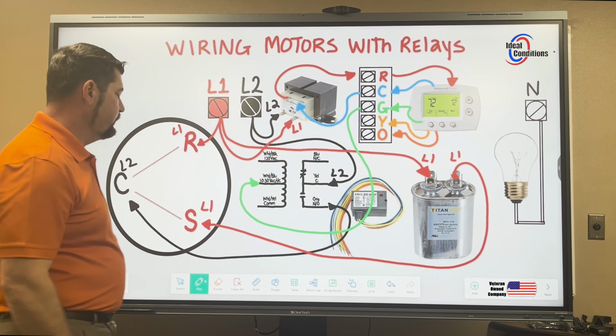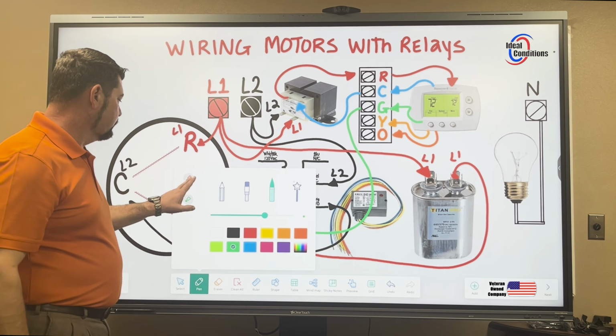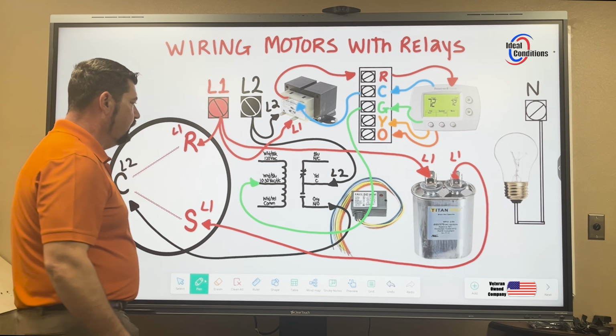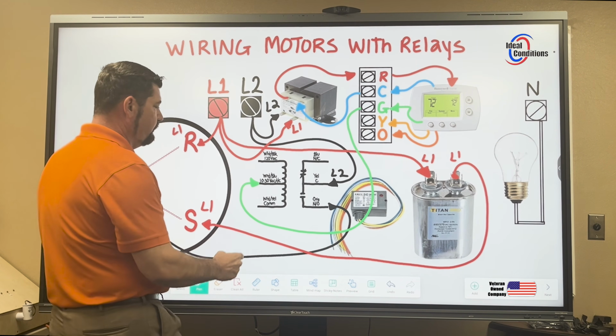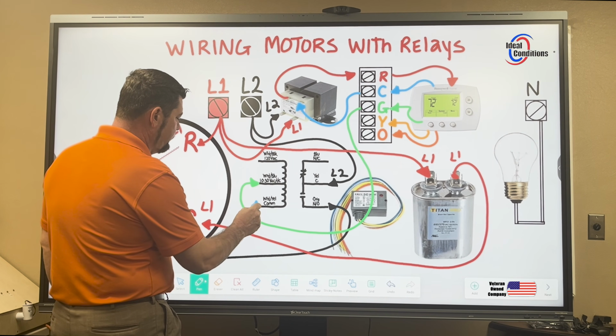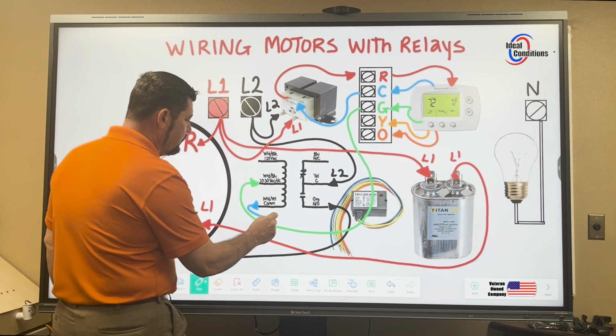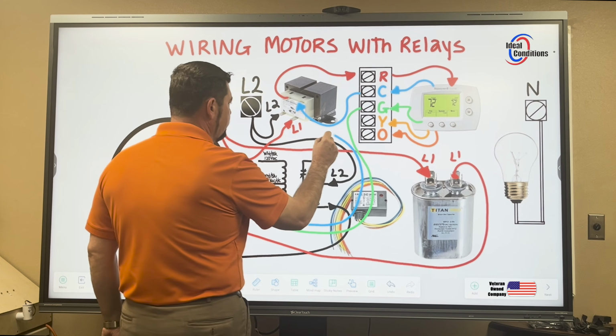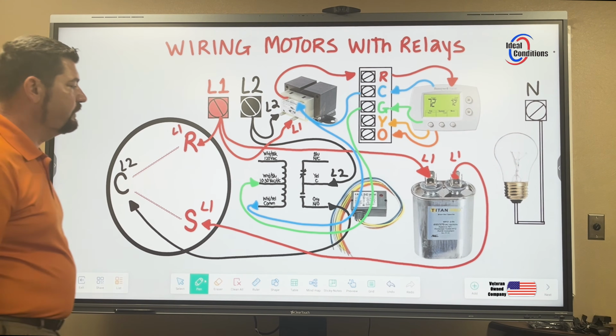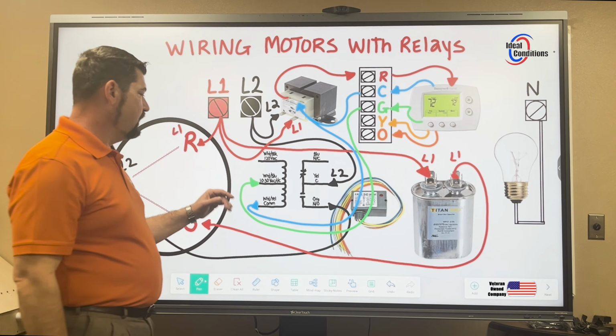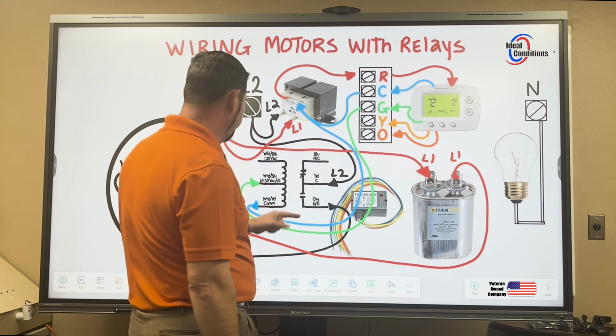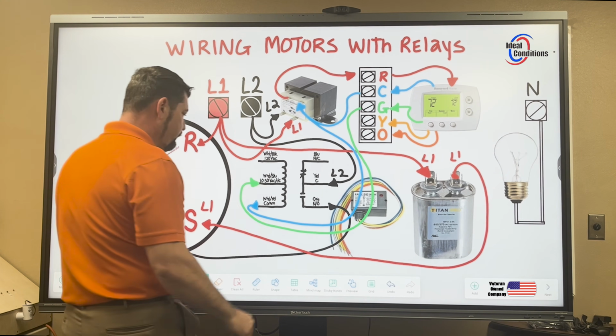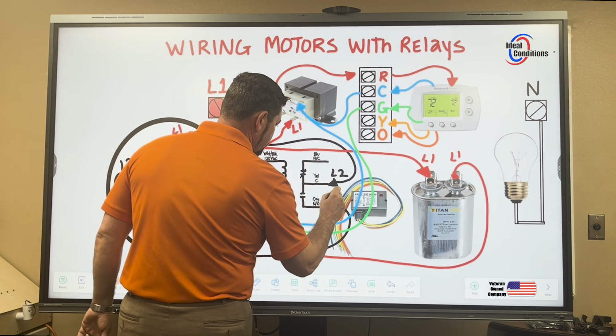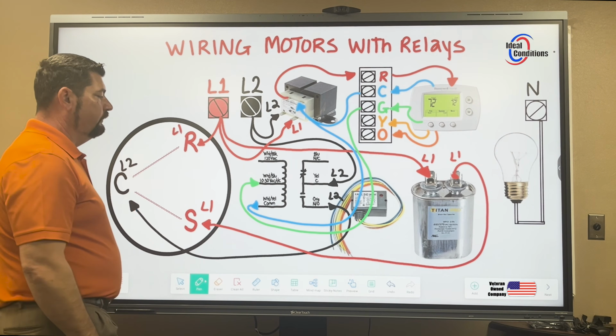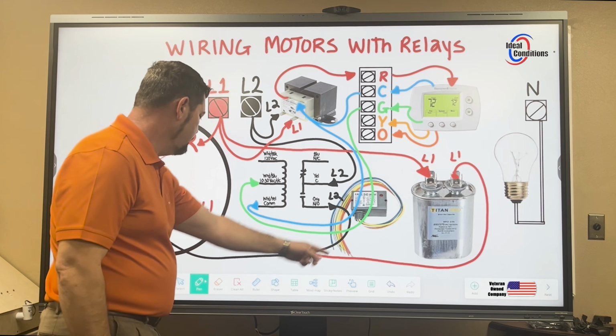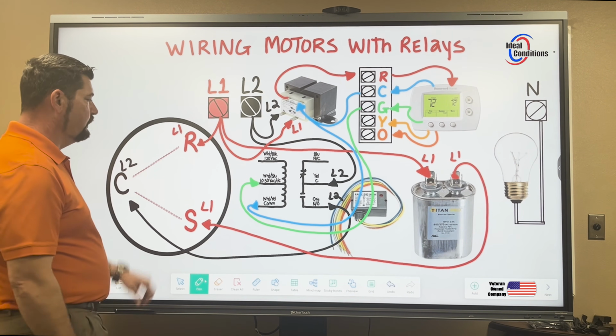You have wires all over the place. That's why I try to color code this as best as possible, to try to confuse you the least amount. I'm going to take my common as an output out of my coil, run it back up this way and join that with my common on my transformer. At this point in time, I now have coil voltage, so L2 can come over and be present right here. So this will close, this will open, and L2 will come on and will energize the motor.